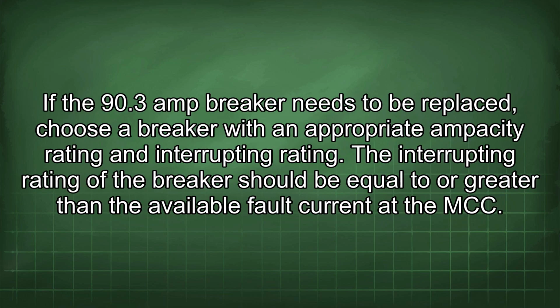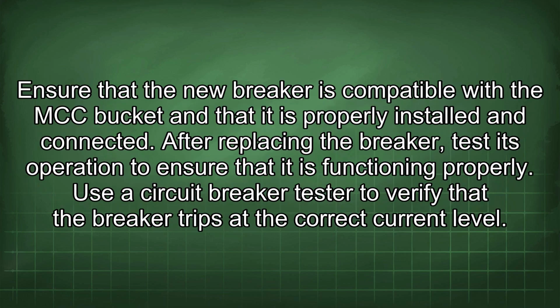If the 90.3 amp breaker needs to be replaced, choose a breaker with an appropriate ampacity rating and interrupting rating. The interrupting rating of the breaker should be equal to or greater than the available fault current at the MCC. Ensure that the new breaker is compatible with the MCC bucket and that it is properly installed and connected. After replacing the breaker, test its operation to ensure that it is functioning properly. Use a circuit breaker tester to verify that the breaker trips at the correct current level.